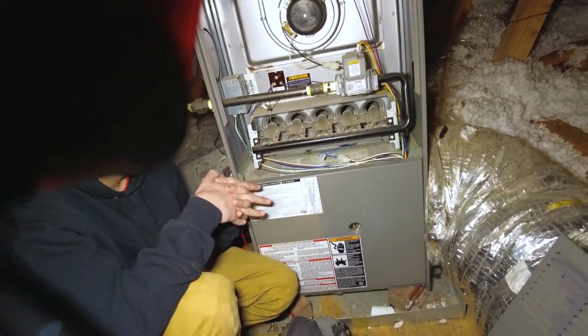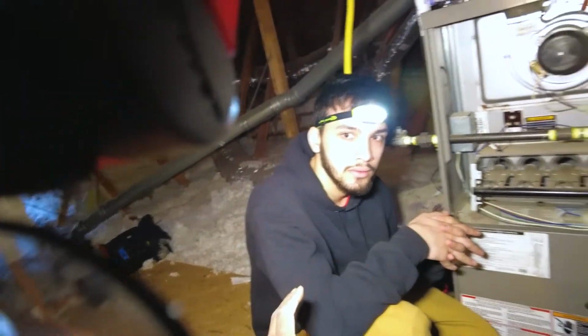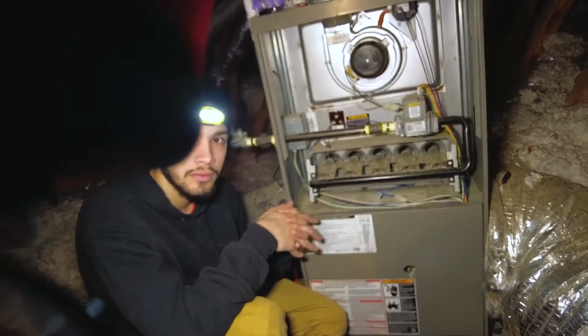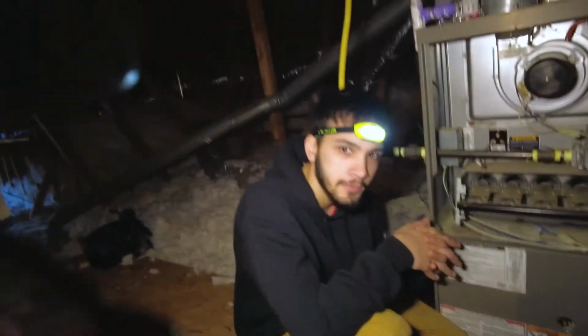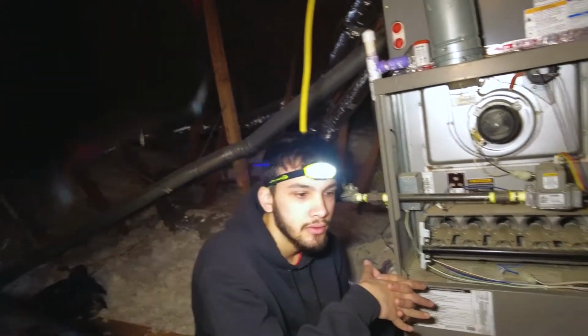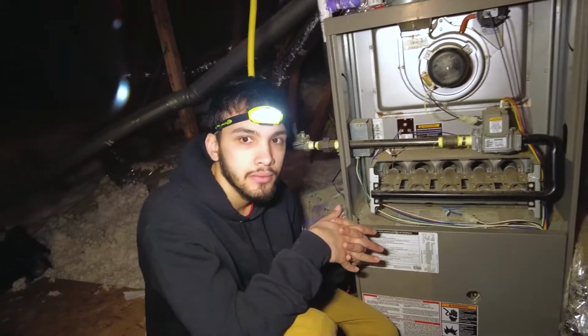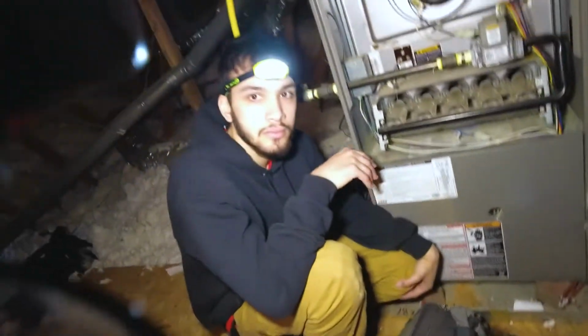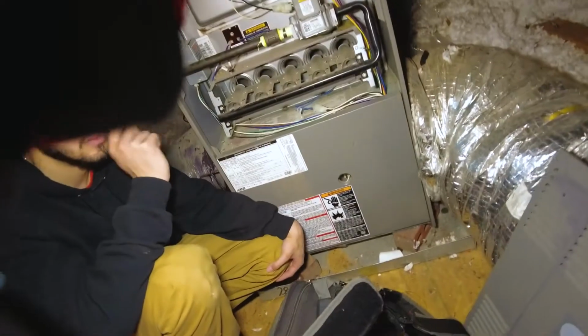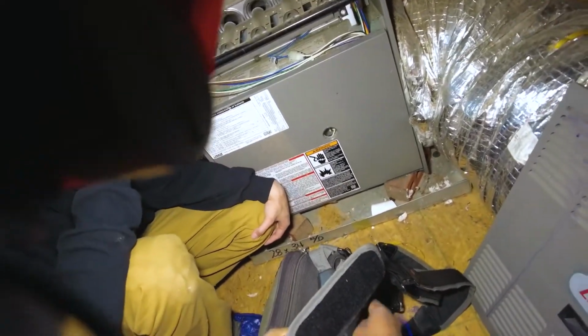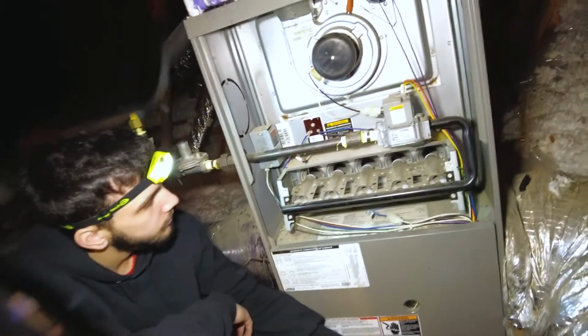Usually we do want to do a brief check. If we see it above 0.7, 0.8, we're going to want to do some inspecting of the ductwork. Usually here in the Carolinas, it's due to being undersized. I'd say probably 80-90% of the furnaces in the Carolinas are going to have undersized ductwork.